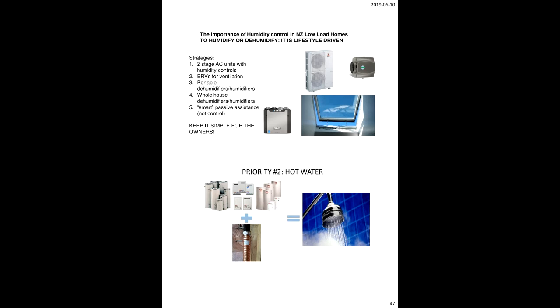Okay, importance of humidity control. Some other things to consider to control this that you can look at: air conditioning. Don't do anything less than 2-stage units at minimum, so it can actually slow down a little bit and get a proper cycle time. In some cases, if you go with mini splits or multi splits, they actually have dehumidification cycles that can do that alone, and they're great for ERVs. Nice option: whole house humidifiers, dehumidifiers, ERVs.